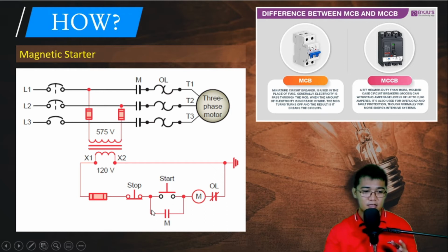Now, the only way to stop the motor from running is when we press this normally closed push button. Pag pinindot natin to, there will be no flow of current through our coil, so magde-de-energize, this one will go back to its normal state, magiging open ulit, walang kuryente na mag-flow sa ating motor. Or, another way is, pag nag-overcurrent ang ating motor, this will trip, this will open, de-energize pa rin yung ating coil.